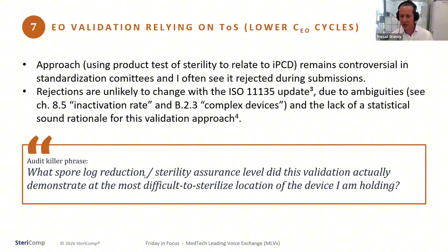So now quickly, if your recent validations relied on this approach, the potential downstream costs if challenged are: you must repeat the validation, and if it fails, and this is very likely, if you put the BI at the worst case location, then you must develop a new cycle and do a validation again. And maybe you did your packaging and product testing with this initial process, so maybe you have to do this again because now you have a process with more EO concentration or longer EO dwell times and so on. So you definitely have high submission delays and very high costs.